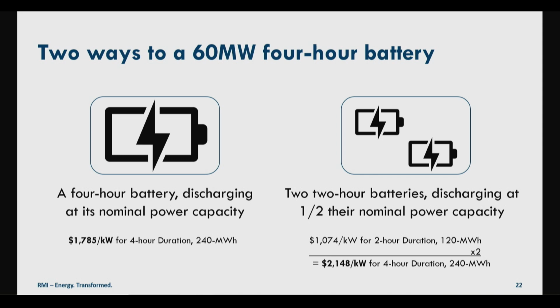Another way that we can get 4 hours of energy would be, for example, to take a single 2-hour battery and discharge it at 50% of its power capacity. This could give us 4 hours of energy, but if that's another 60 megawatt battery, it would be producing only 30 megawatts of power. So this really isn't an apples to apples comparison, because one battery would be discharging at 60 megawatts, the other battery would be discharging at 30 megawatts.